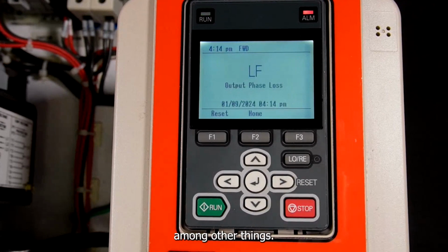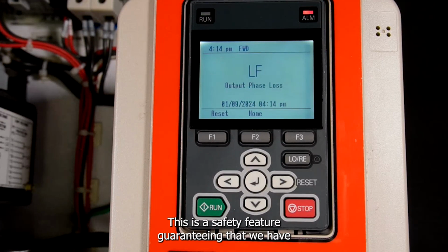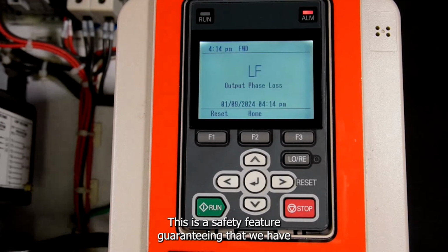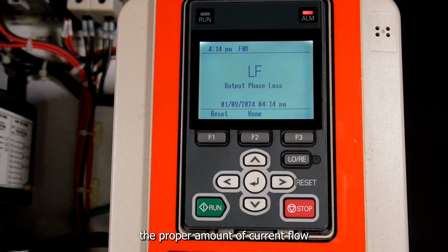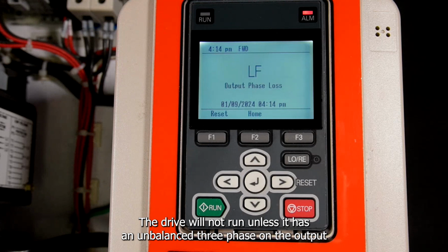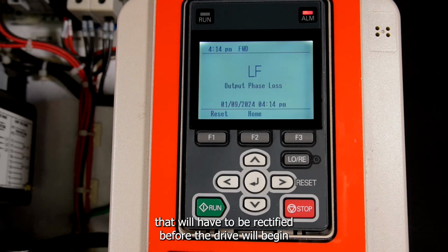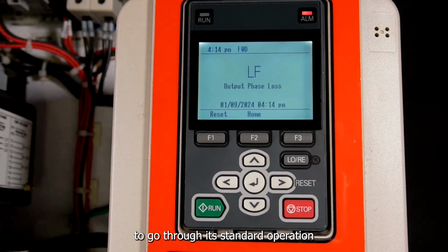Among other things, this is a safety feature guaranteeing that we have the proper amount of current flow to the motor that will safely control the load. The drive will not run unless it has a balanced three-phase on the output. That will have to be rectified before the drive will begin to go through its standard operation cycle.